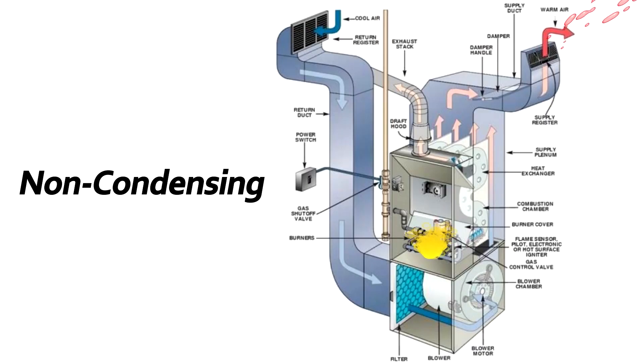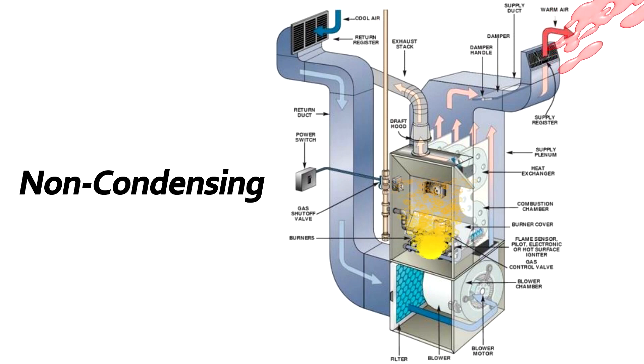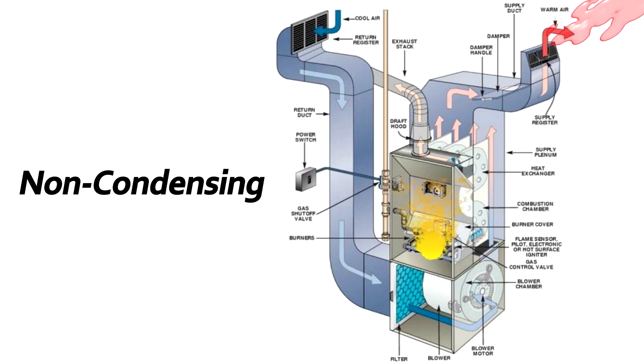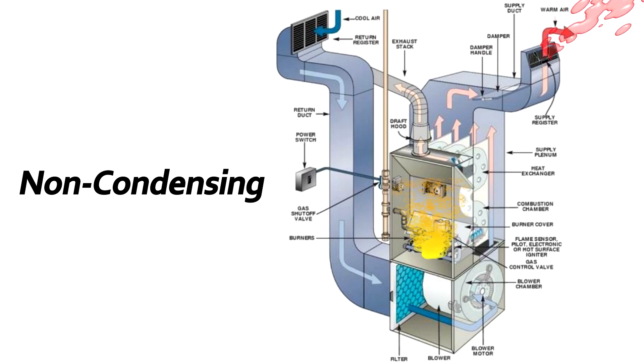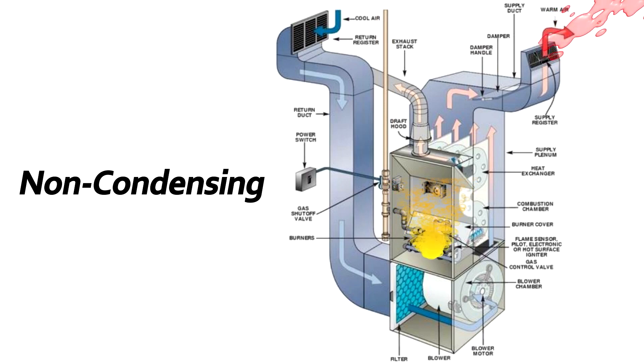Condensing water heaters also have a secondary heat exchanger that can reuse exhaust heat to heat the water even better. Non-condensing water heaters vent exhaust gases outside, and they burn at a high enough temperature so there is zero condensate left in the system. A non-condensing water heater needs metal venting to manage the extra heat, which would be Z-Flex venting.